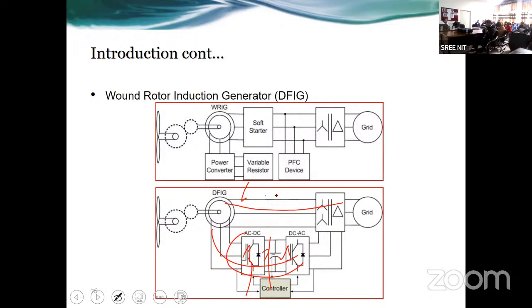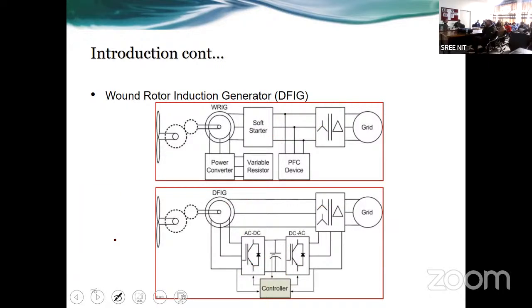Because the rotor is allowed to change its speed by 30 to 40%, a speed variation of 30 to 40% is available, so you can change the speed of the machine to extract maximum power. While in this other case, it is fixed speed wind turbines. Of course, some gearbox is required to boost up the speed in order to reduce the number of poles or the size of the machine. The higher the RPM, the smaller the size of the machine or generator. The lower the RPM, the larger the size of the machine.